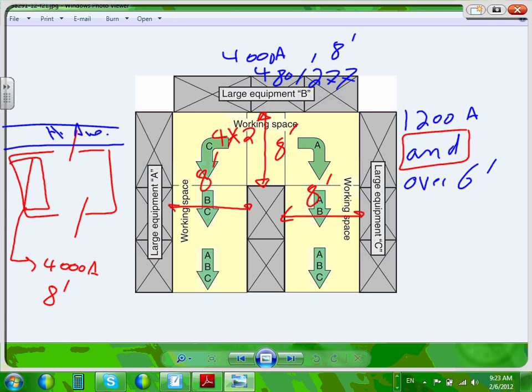So you have to have two entrances. But can I get you guys to understand what system we are talking about? 1200 amp, big major equipment. Do you remember, guys, what we talked about, 1200 amp? 1200 amps are panel boards. You're getting into the end of the panel boards. You're getting into almost switchboard design, big equipment. Okay, so that's for major equipment.